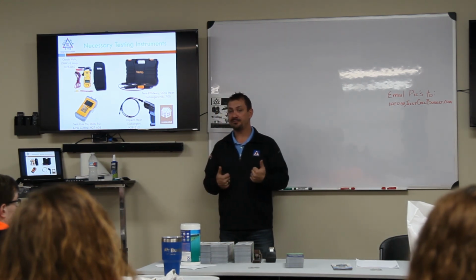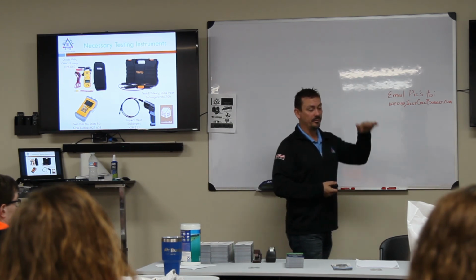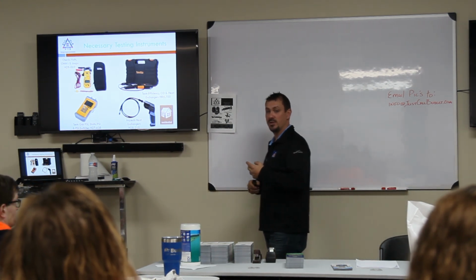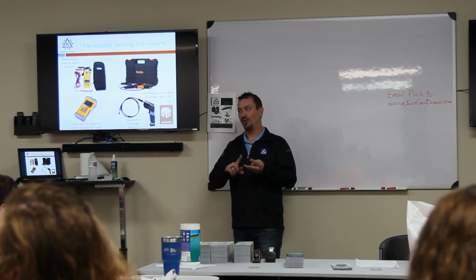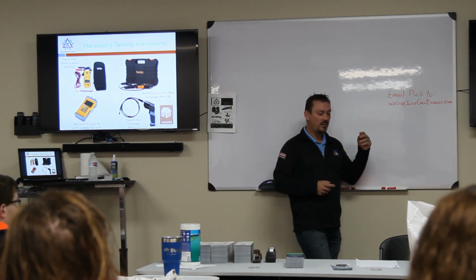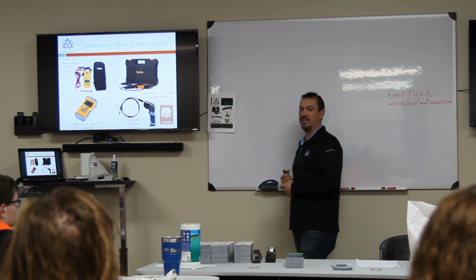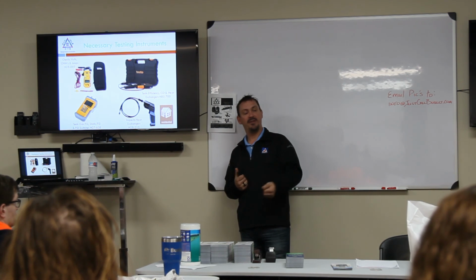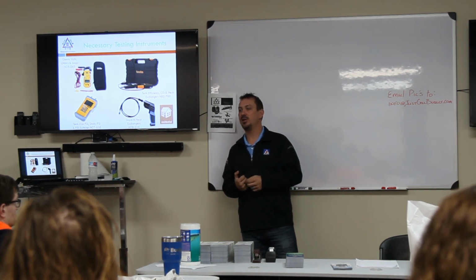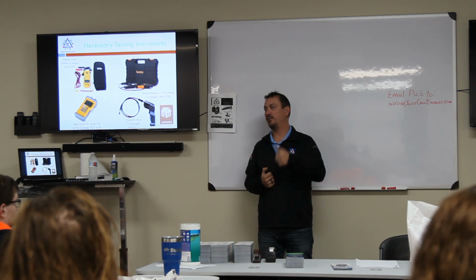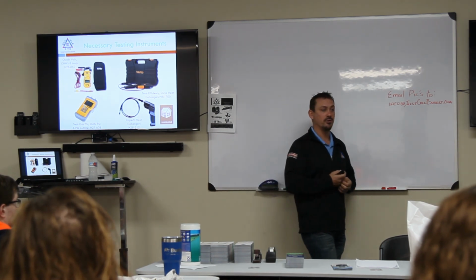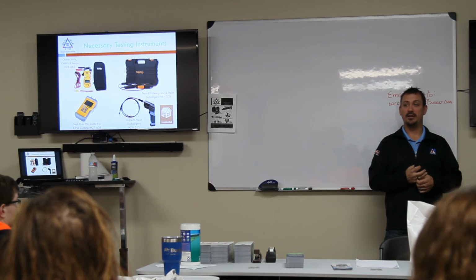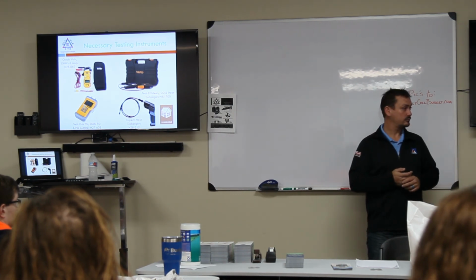We turn the furnace on. As the furnace heats up, it burns the oxygen off, because the flame needs three things: oxygen, fuel, and an ignition source. And as it's burning that oxygen, the oxygen levels will drop, and let's say it drops down to 9.2%. And then if the blower kicks on and there is a crack in that heat exchanger, your oxygen levels will start to rise. If your oxygen level rises when doing this test, then you can start to look further and see that there's a crack in the heat exchanger.